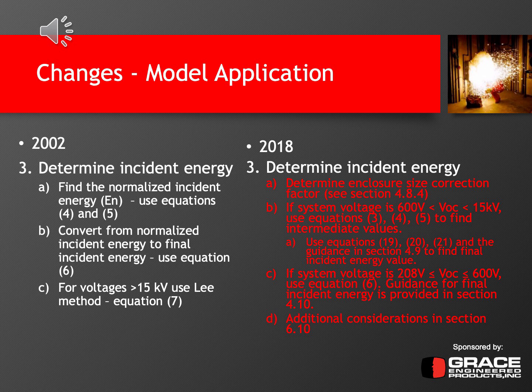So if you're doing calculations at a 480 volt system, your incident energy calculation would be a little bit simpler than if you did calculations at a medium voltage system or something above 600 volts. And then there's some other language in the standard that says additional considerations should be evaluated, and some other guidance has been provided in section 6.10.